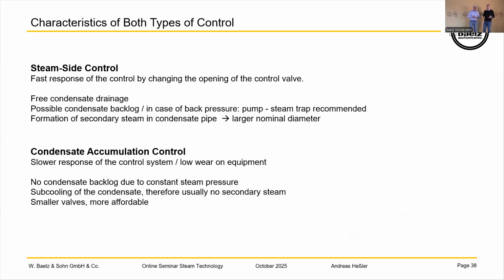So the condensate side control is the BAELZ standard, because it's more efficient and a better solution. You need less steam. So we have this as a standard, but if the customer really wants to have a steam control, we can do it, of course, for example for fast process heating. All right, thanks, Andreas.